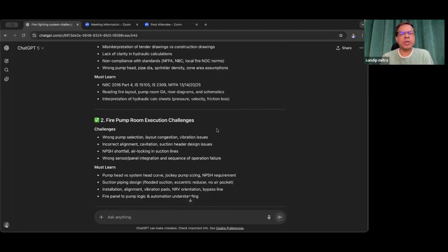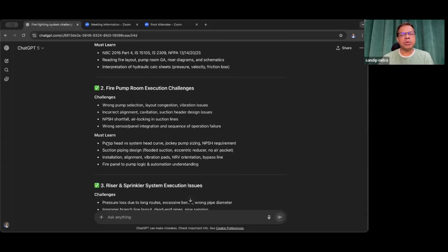What are the challenges in the fire pump room? Wrong pump selection or layout congestion, vibration issues, then incorrect alignment, cavitation, suction header design issue, NPSH shortfall, air locking in suction line, and wrong sensor or panel integration and sequence of operation failure. So how to mitigate? You must learn about pump head versus system head curve, jockey pump sizing, NPSH requirement, suction piping design, flooded suction, eccentric reducer, no air pocket, installation alignment, vibration pads, NRV orientation, bypass line, fire panel to pump logic, and automation understanding. So many things you need to learn.